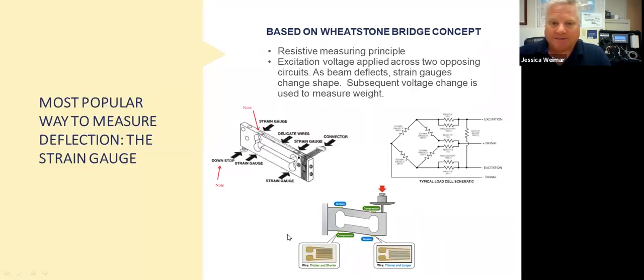I've got to click to the next slide. Most everybody in this industry knows of what's called a strain gauge load cell. Strain gauge load cells, just like we talked about a minute ago, take a load, and as that load changes, you'll see it right down here in the middle of the slide, the beam deflects. In a strain gauge load cell, they use something called a Wheatstone bridge circuit that's adhered to the side of the load cell. As that beam deflects, the shape of the Wheatstone bridge changes, and it changes the electrical resistance across that bridge. Measuring the change in electrical resistance gives you the ability to measure weight.